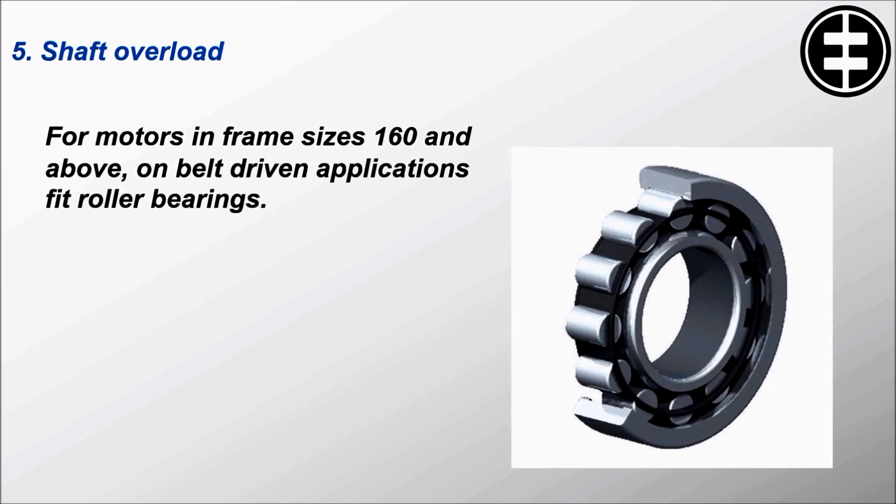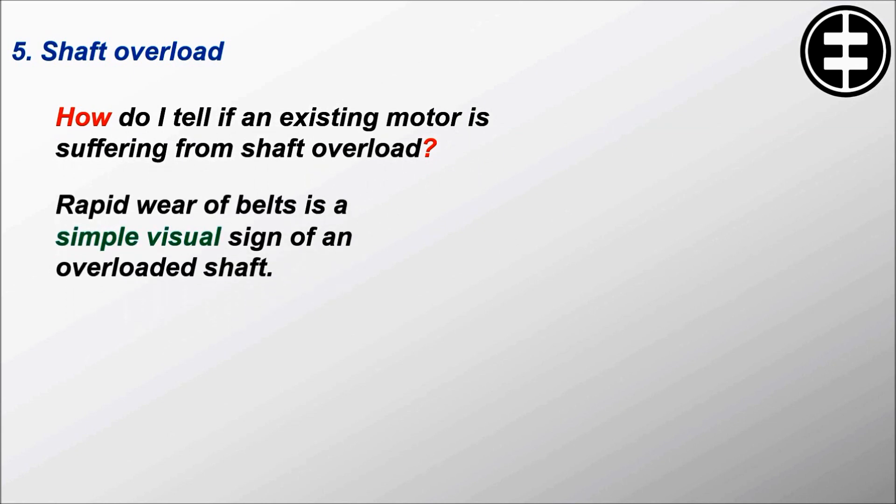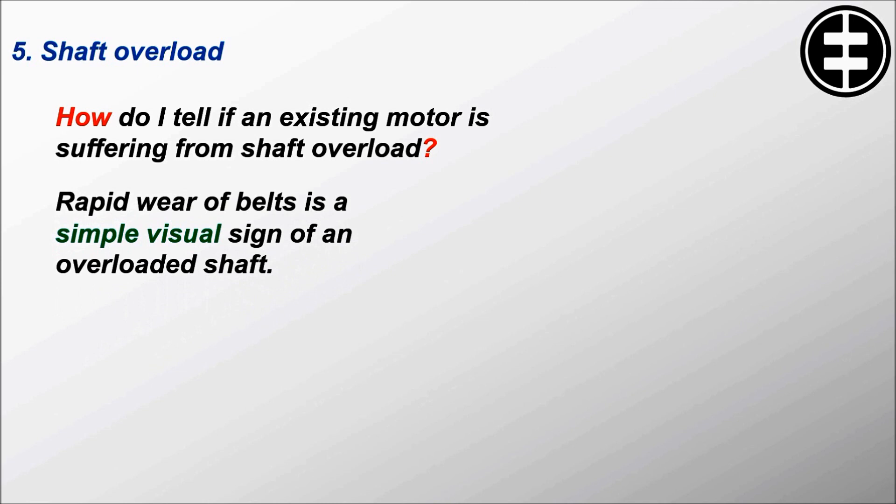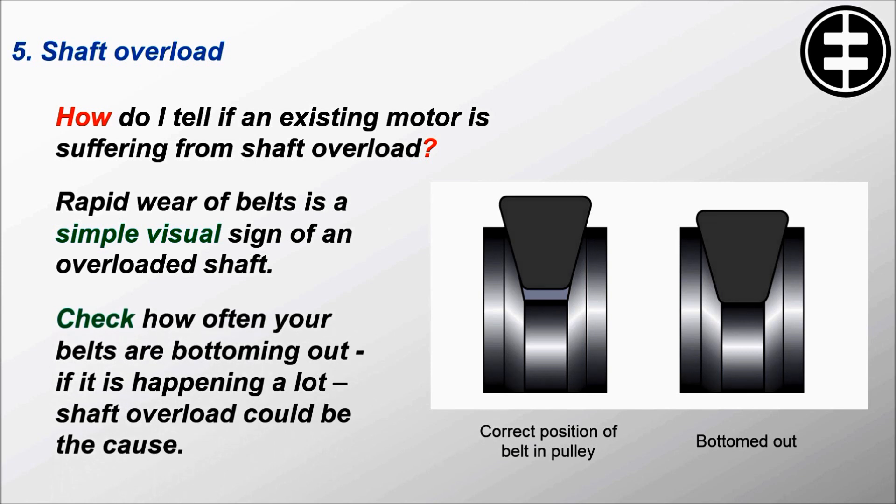How do I tell if an existing motor is suffering from shaft overload? Rapid wear of belts is a simple visual sign of an overloaded shaft. Check how often your belts are bottoming out. If it is happening a lot, shaft overload could be the cause.